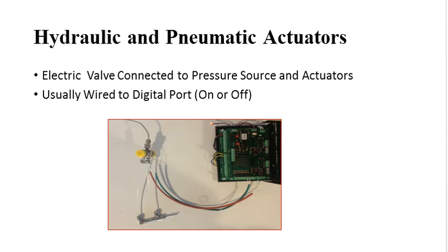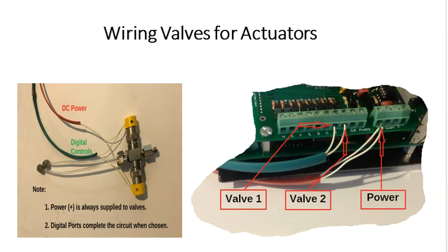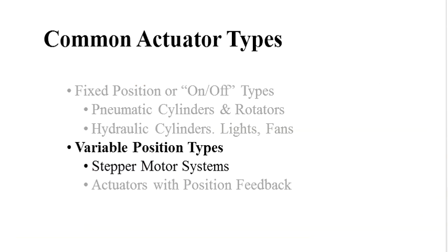Similarly, actuators, for example, multiple actuators that are used for a variety of cases, will use more than one port. In this case, there's two solenoid valves that make this particular actuator move out and back and vented in each position. It's wired up in a fashion like this. The two lines are the common power lines that go to each of the two solenoids, and then the two separate solenoid valves come back to two separate ports on the DAQ2GO, and those are addressed individually to make the action that you desire actually happen.